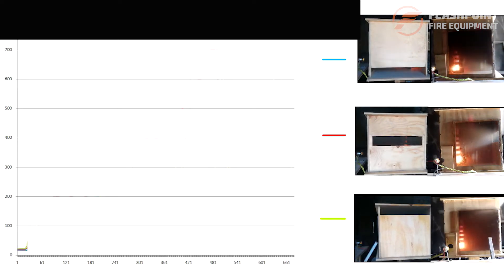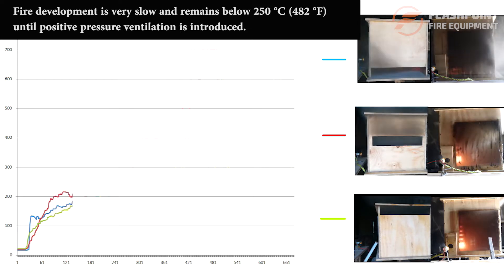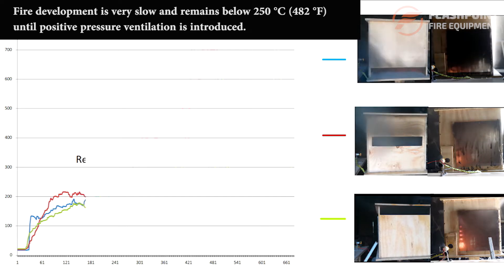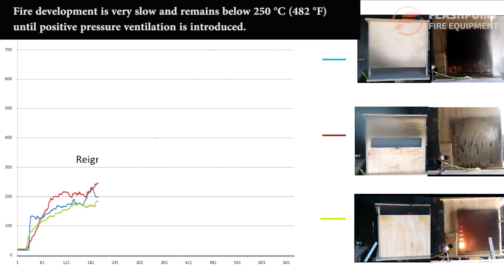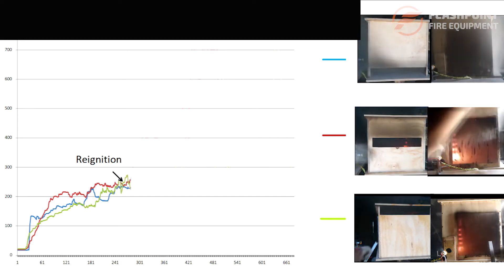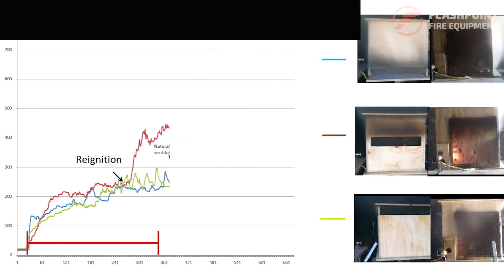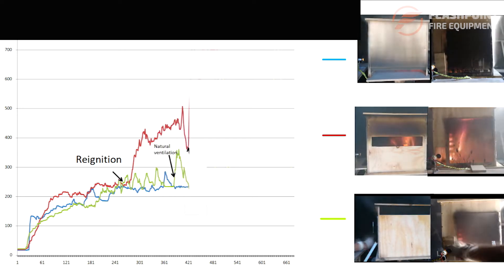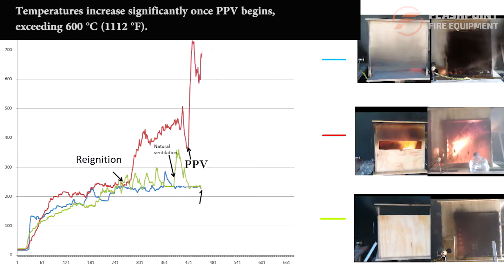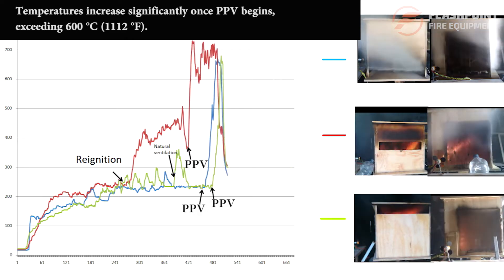With the opening positioned horizontally at various heights for comparison in the first series of burns, fire development is very slow and remains below 250 degrees Celsius until positive pressure ventilation is introduced. Temperatures increase significantly once PPV begins, exceeding 600 degrees Celsius, or 1112 degrees Fahrenheit.